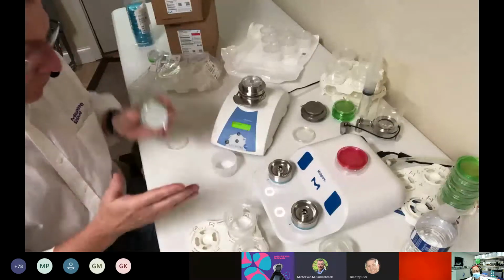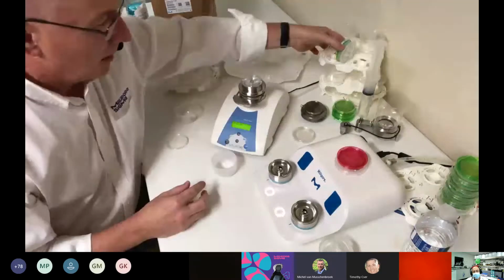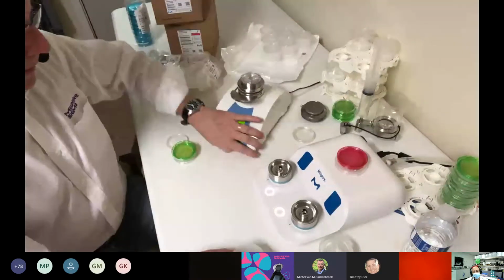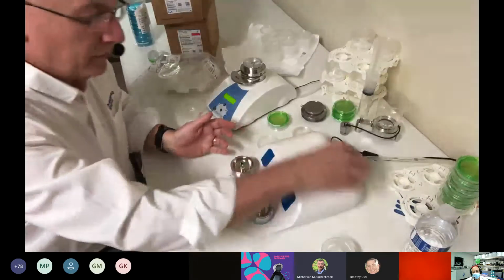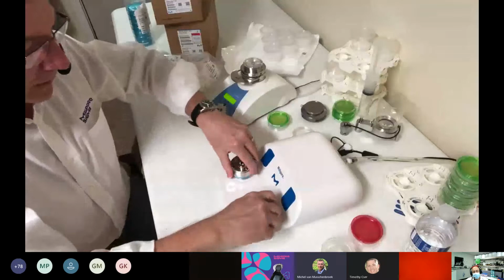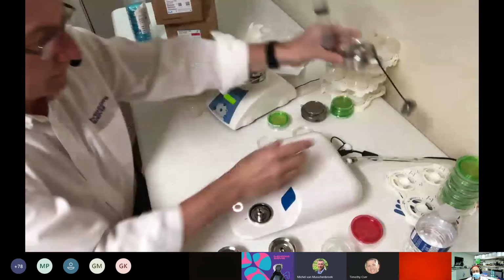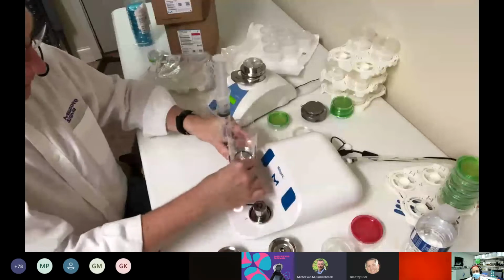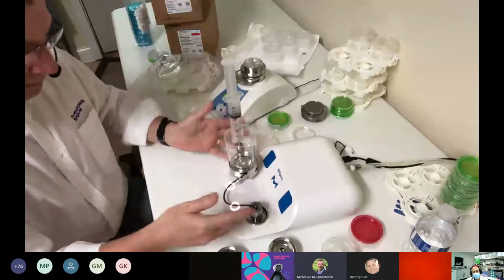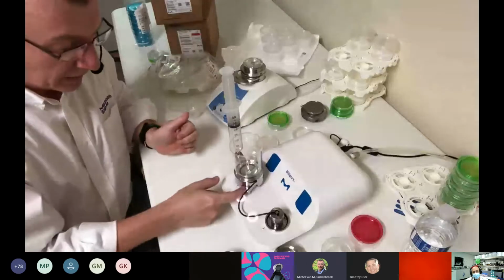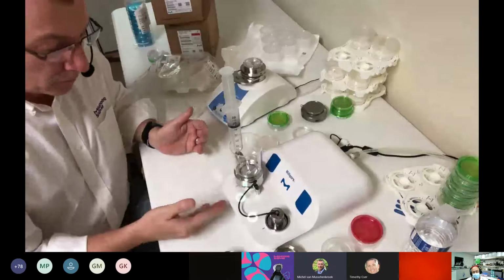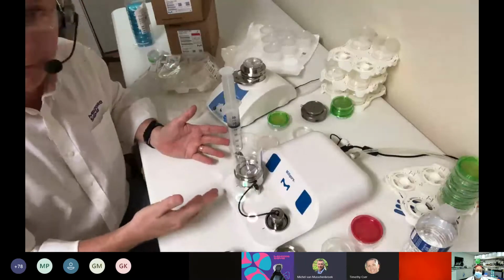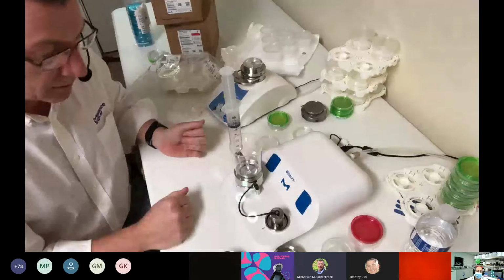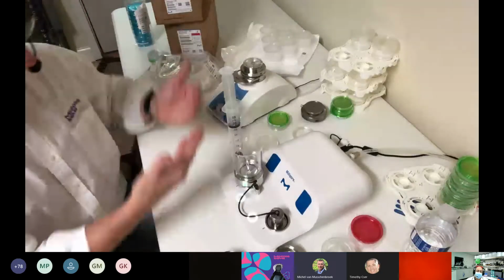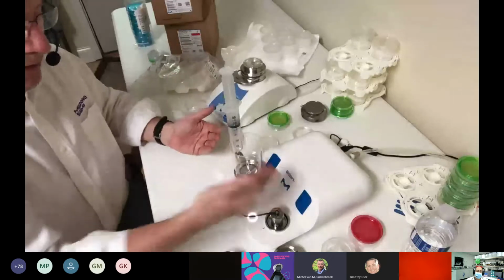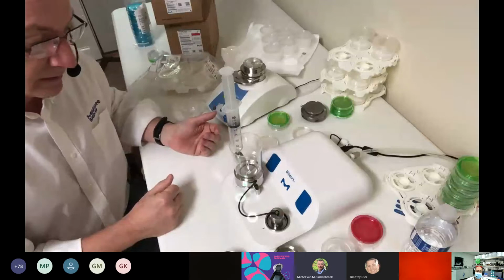So it's really quite a simple system, and we've really worked on making it faster and easier for you. I said I would show you very briefly what the sanitization would look like. The video really showed how simple it was, but I want you to just see it's just a matter of removing the pump heads, putting the top for the other side, and this way I have my closed unit. And I'm not sure if the light will show, but as I move that lever over, it turns green. When it turns green, it identifies for the system that this is now ready for the sanitization, and we're ready to go. It's a matter of pressing that, and it would go through that 15-minute cycle where it draws the plunger through, gives you the hold time, and then flushes it with the sterile water that's in there.